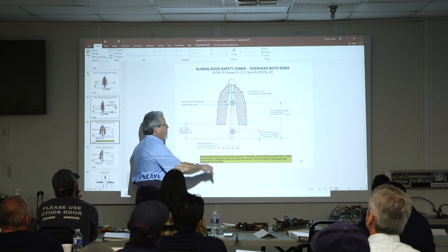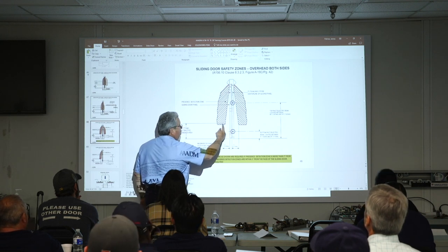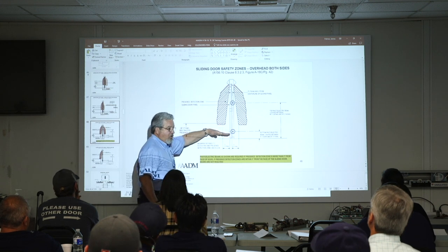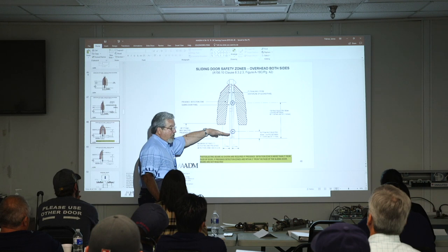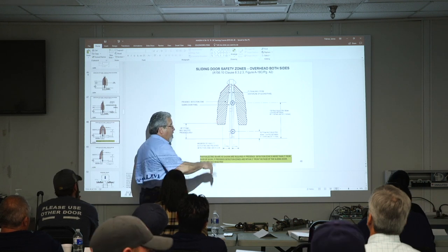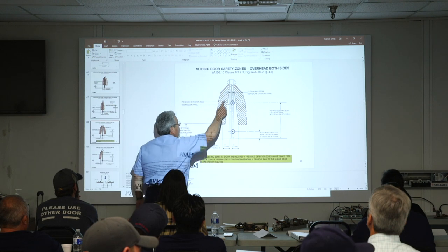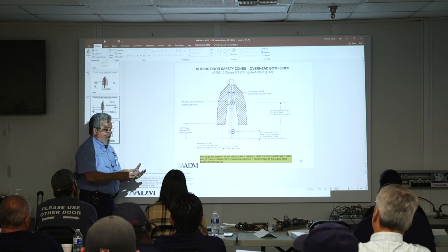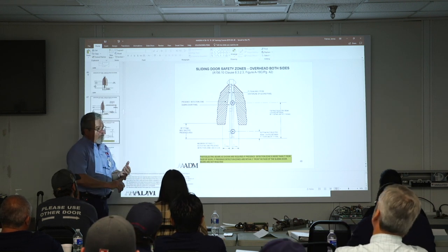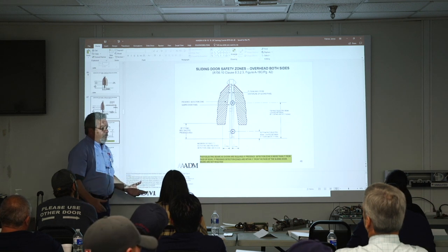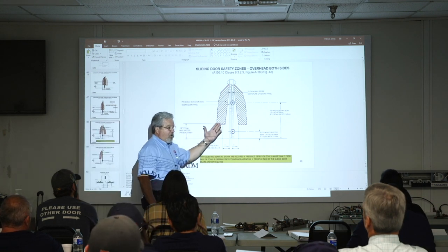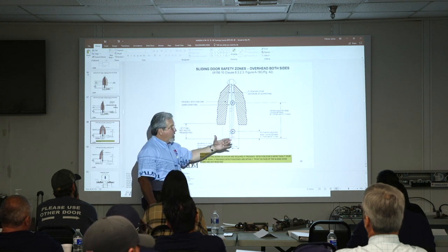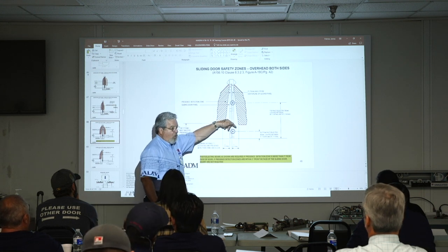So this represents what the presence zone would look like for a sensor like that, meaning that it has to project out from the face of the door a certain distance, and it has to be within, there's that 28 inches again, of the floor. It's okay if you bring it down to 6 inches of the floor, if you can, but that's the minimum you could have. What's not seen here is the activation zone, farther out, so that as you approach the door, the activation zone, which in today's sensors might be microwave or active infrared, depending on the manufacturer, causes the activate signal to get the door open. And then the presence zone keeps the door open while a person is going through the doorway, across the threshold.